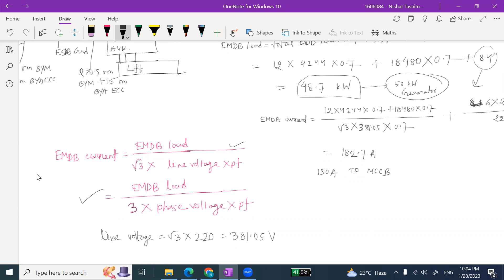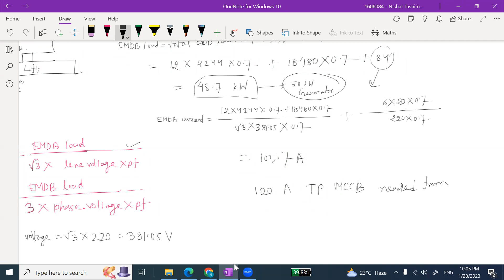Okay, now calculate the current. Ma'am, 105.7. I was also wondering the current value should not be that high. 105.7. 105.7 ampere. Now for 105.7 ampere we can use 120 ampere, right? So we can write a 120 ampere triple pole circuit breaker needed from EMDB to MDB.